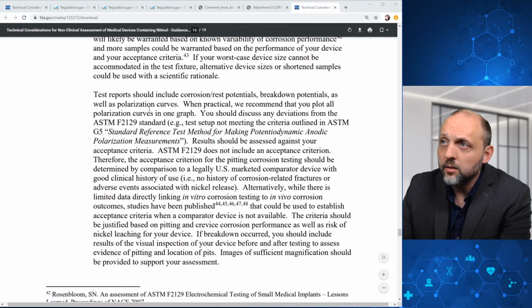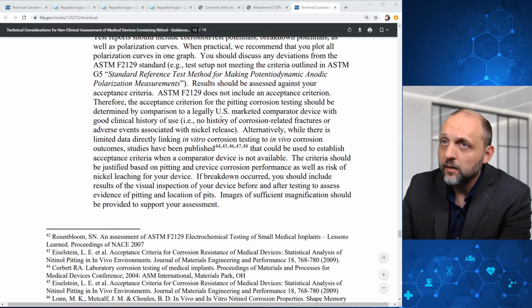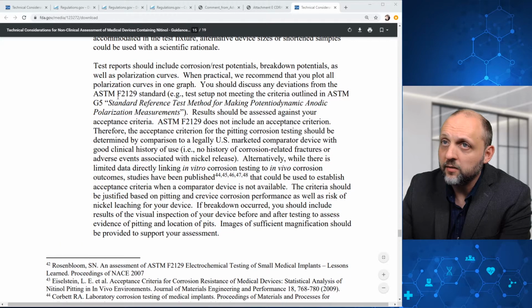And then here, FDA calls out that test reports should include corrosion and rest potentials, breakdown potentials, as well as polarization curves. And when practical, they recommend that you plot all polarization curves in one graph and discuss any deviations from ASTM F2129.